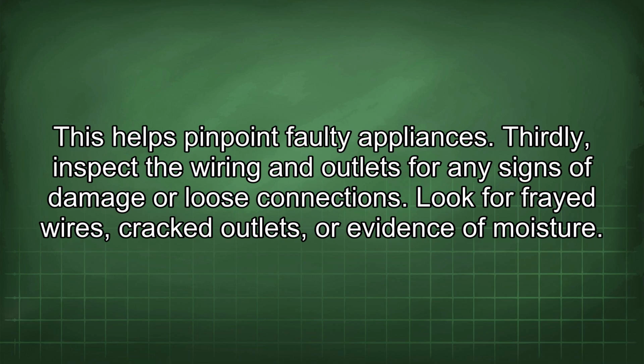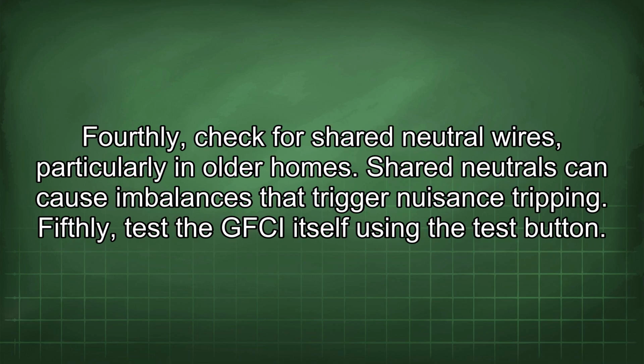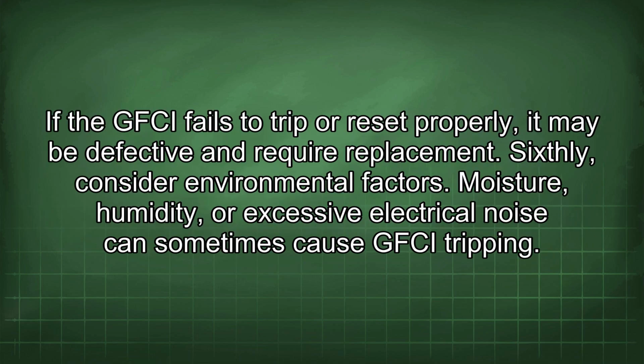Thirdly, inspect the wiring and outlets for any signs of damage or loose connections. Look for frayed wires, cracked outlets, or evidence of moisture. Fourthly, check for shared neutral wires, particularly in older homes. Shared neutrals can cause imbalances that trigger nuisance tripping. Fifthly, test the GFCI itself using the test button. If the GFCI fails to trip or reset properly, it may be defective and require replacement. Sixthly, consider environmental factors. Moisture, humidity, or excessive electrical noise can sometimes cause GFCI tripping.